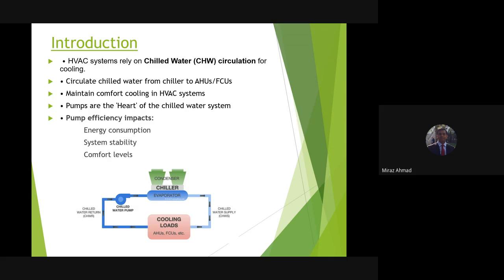One question: closed loop? You mean to say the water will not be lost anywhere? No, there will be a loss of water within the system, of course, because of evaporation and leakages. So there is a system called a pressurization unit, which consists of pumps to pump the water, and a break tank, which always has water inside. And then there is a pressure vessel to maintain both the pressure and the water across the chill water system. So all the losses are made up by the pressurization unit.